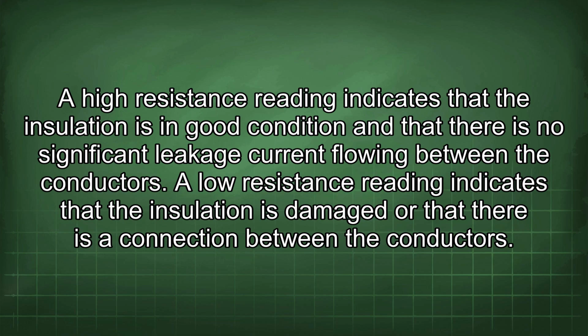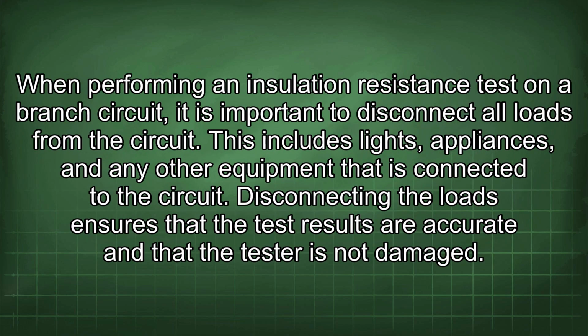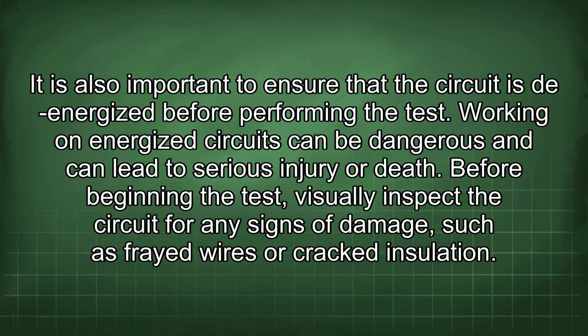When performing an insulation resistance test on a branch circuit, it is important to disconnect all loads from the circuit. This includes lights, appliances, and any other equipment that is connected to the circuit. Disconnecting the loads ensures that the test results are accurate and that the tester is not damaged. It is also important to ensure that the circuit is de-energized before performing the test. Working on energized circuits can be dangerous and can lead to serious injury or death.